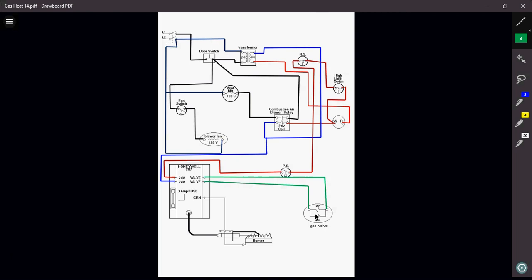Once the furnace cools off enough, my fan switch is going to open, usually probably about 100 degrees or so, maybe 120, depending on where it's set. Once that opens, my blower fan is going to shut off, and the furnace is now at rest, waiting for the next call for heat to occur. And once that happens, the entire sequence of operation starts all over again, and the furnace will light off. And that's how you wire a spark ignition system with an inducer motor.